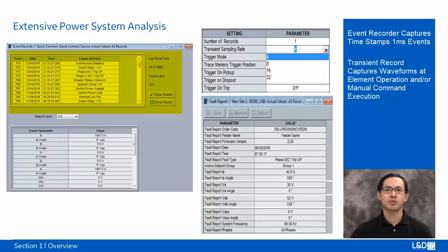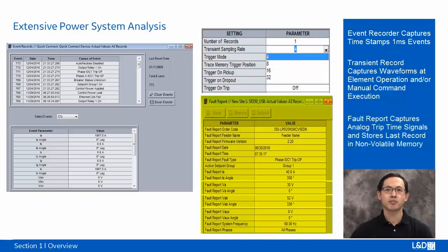Event recorder of 1 millisecond time stamping records the sequence of events and relevant parameters. Transient record captures the waveform as an instance of element operation, input, or manual command. The fault report captures analog signals at the time of the trip and stores the last recorded values in non-volatile memory.